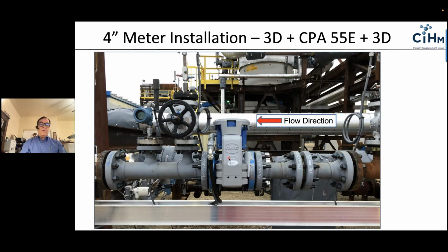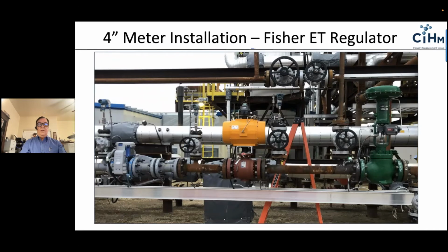So again, the flow is right to left of the downstream section on the 4-inch line. Here's a view a little further back. You can see the metering package here, as we call it in AGA and Measurement Canada. We have an isolation valve here in orange, and then of course the Fisher ET regulator upstream, which is taking roughly 200 kPa of differential for flow control.